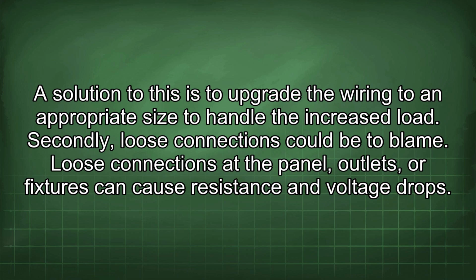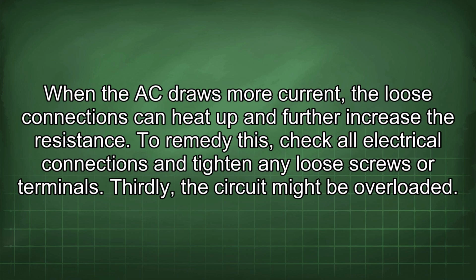Secondly, loose connections could be to blame. Loose connections at the panel, outlets, or fixtures can cause resistance and voltage drops. When the AC draws more current, the loose connections can heat up and further increase the resistance. To remedy this, check all electrical connections and tighten any loose screws or terminals.